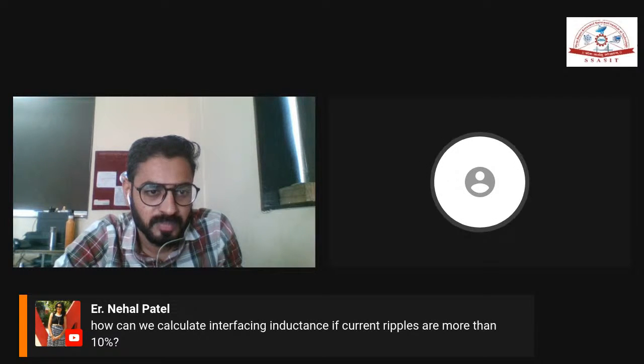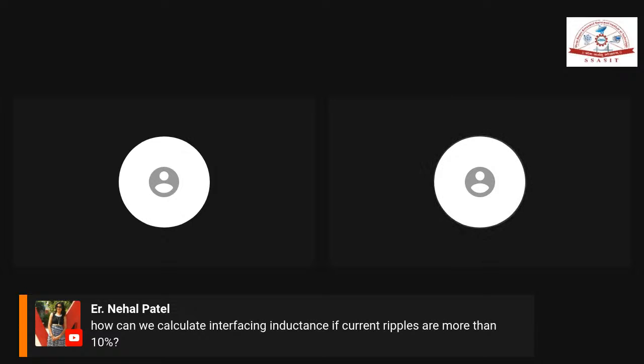How to calculate the interface inductor if the current ripple is more than 10%? Okay, 10% means suppose we have a D-STATCOM current, suppose 10 ampere. So 10 ampere means 10 into 0.1, whatever value will come, that one you can put as the ripple current. If 25%, then 10 into 0.25, whatever value will come, that one you can put as the ripple current. Means if more than 10%, you just multiply whatever the D-STATCOM current comes by 0.1 or 0.2, 0.5, whatever value there is. Okay?